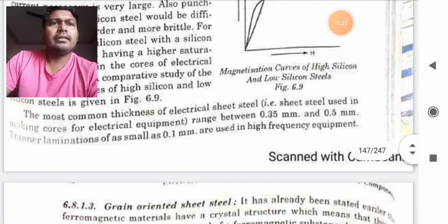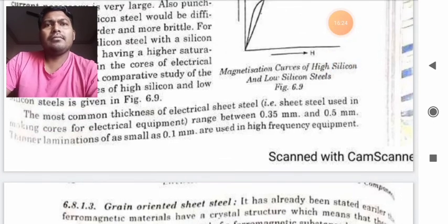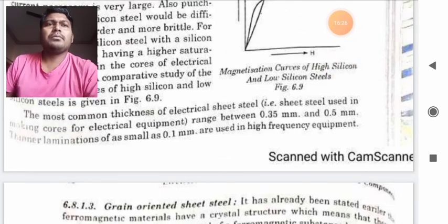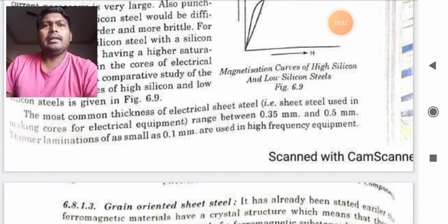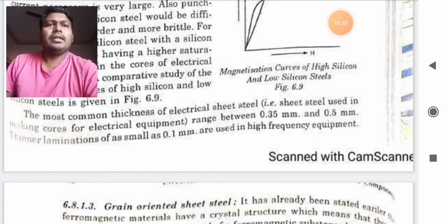The most common thickness of electrical sheet steel in making cores of electrical transformer ranges from 0.35 mm to 0.5 mm. Thinner lamination of as small as 0.1 mm are used in high frequency equipment. In our next class students, we will read about grain oriented steel. Thank you for watching.